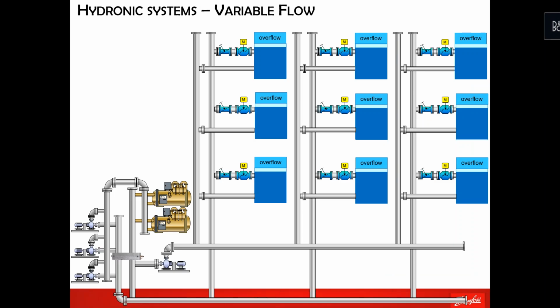So if we want to start at the beginning with the normal two-way system with manual balancing valve. If we have a two-way valve, we need to balance the maximum flow going to every unit in order to modulate that flow based on load demand. But the problem here is those type of valves are a static balancing valve, which means it will be set to only one position and it will be fixed at that position. So if we take this example, if I'm trying to balance this unit, there will be overflow somewhere else.